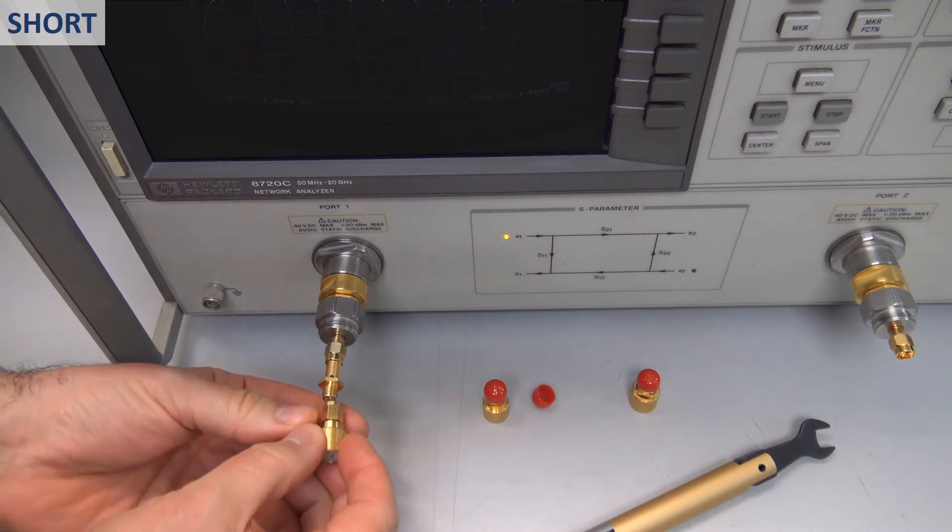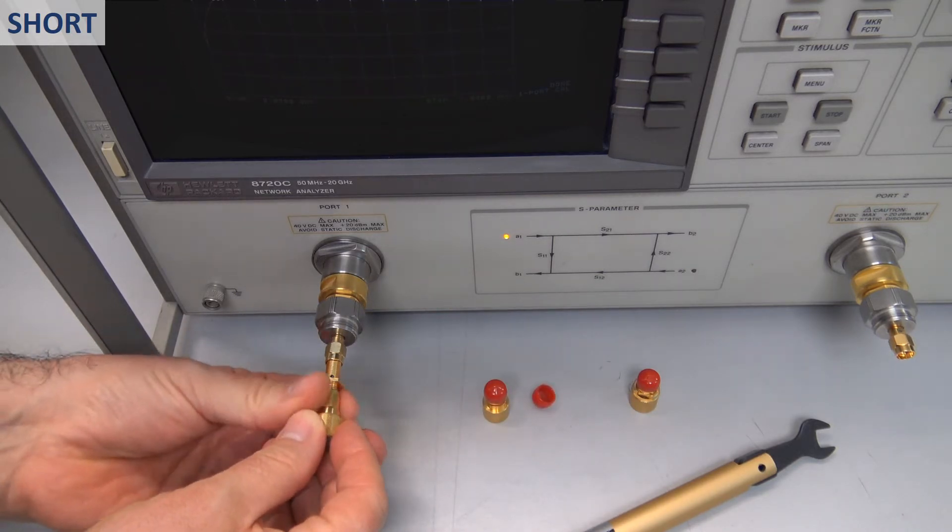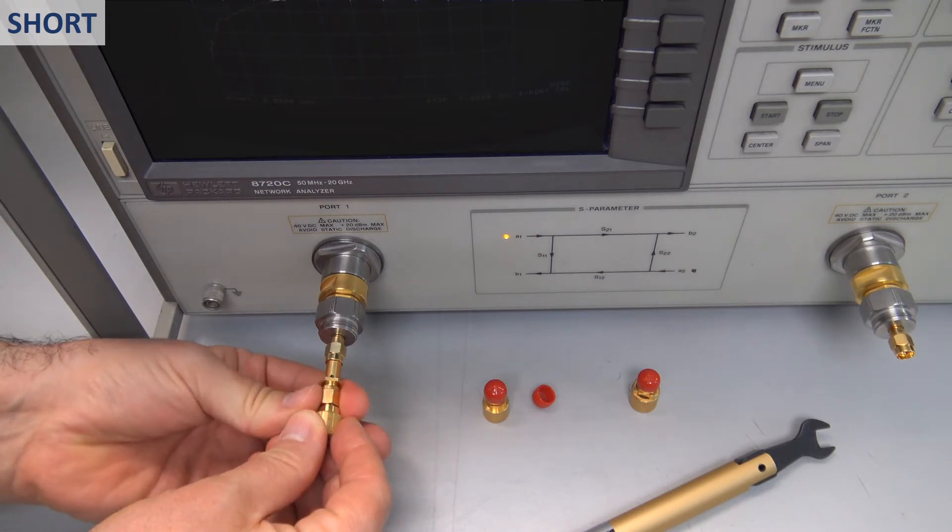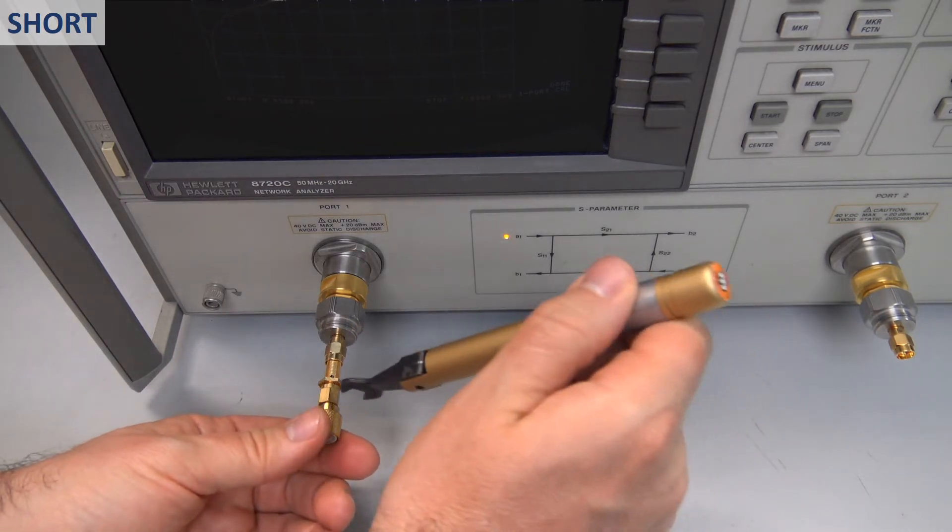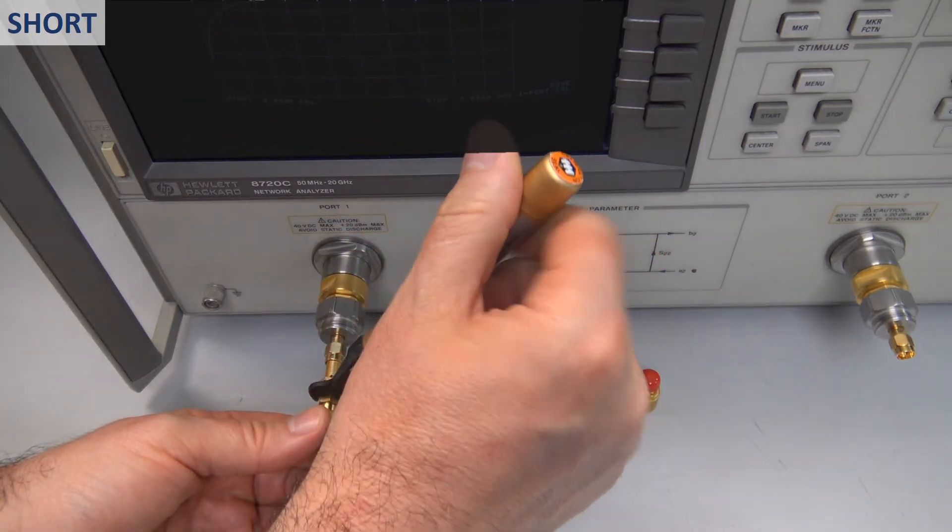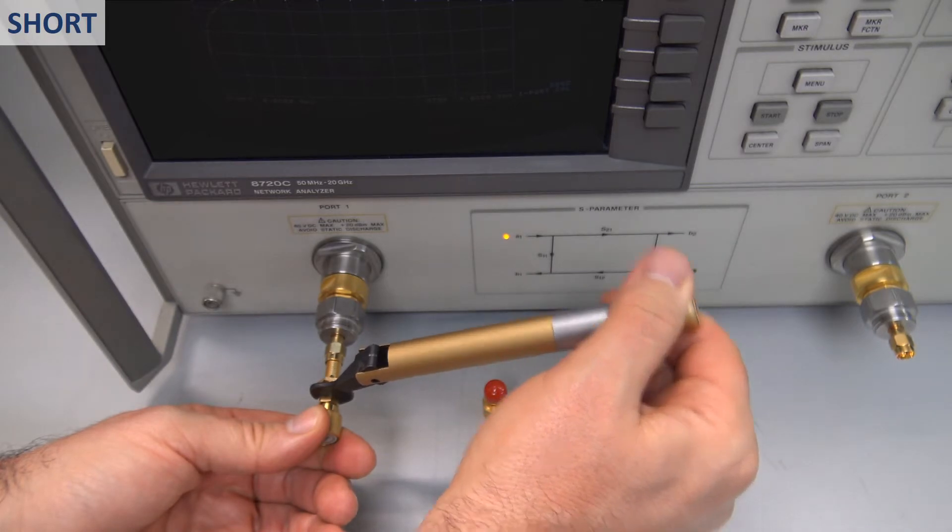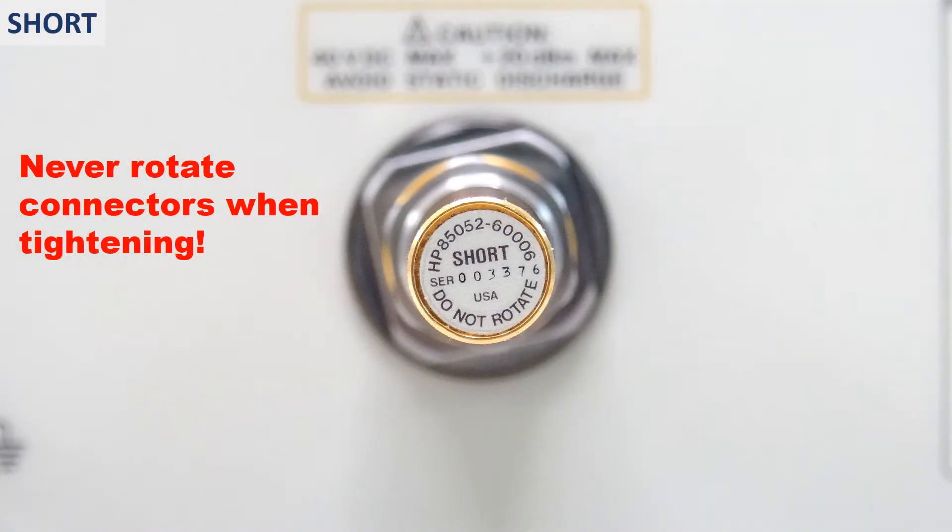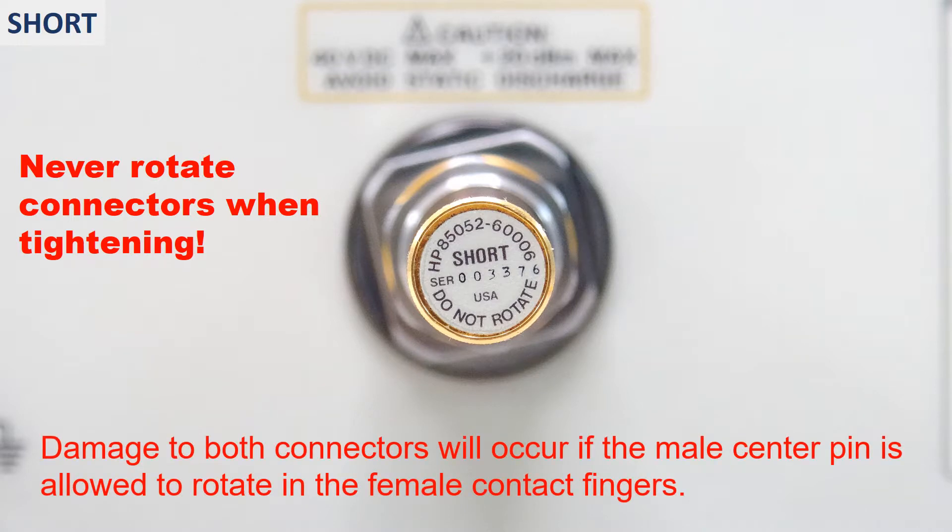Mechanical calibration kits used to come with a calibrated torque wrench. Let us see how to use it. Proper torque on the connector improves measurement repeatability. We hold the torque wrench lightly at the end of the handle and tighten until the break point of the torque wrench is reached. It is particularly important that you rotate only the connector nut, NOT the device or connector body. The connectors might be damaged if the male center pin is allowed to rotate in the female contact fingers.